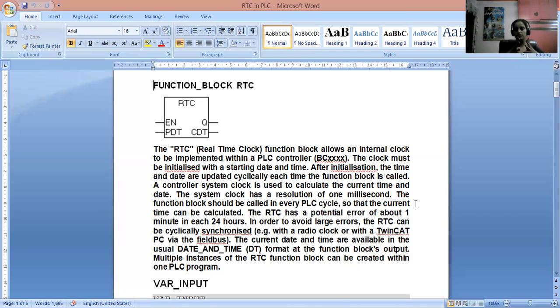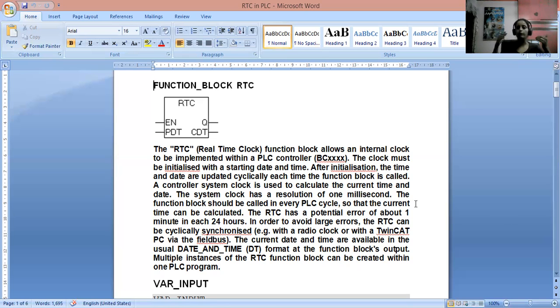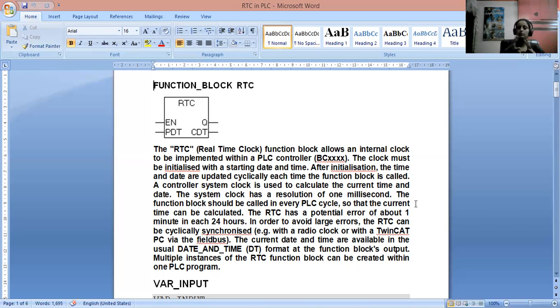If we talk about potential errors, after 24 hours just one minute potential error could be there. There is a chance, but most of the time it doesn't occur. But in order to avoid large errors, the RTC is cyclically synchronized — like a fieldbus or a radio clock — so that we don't have more errors.